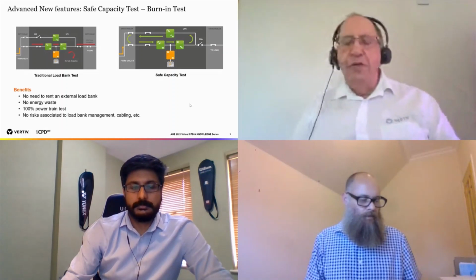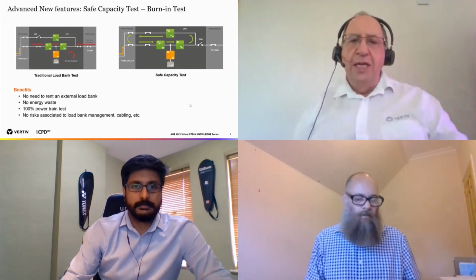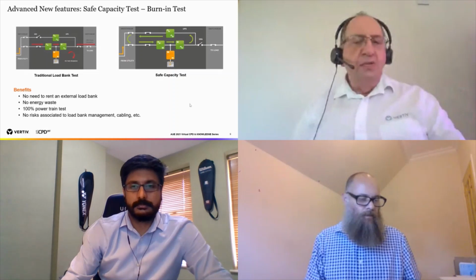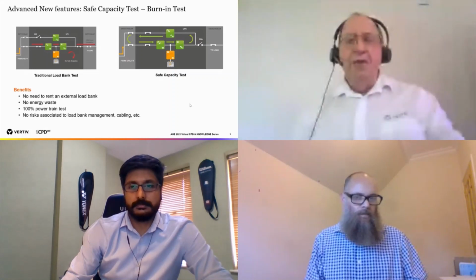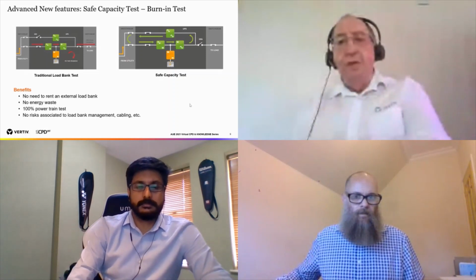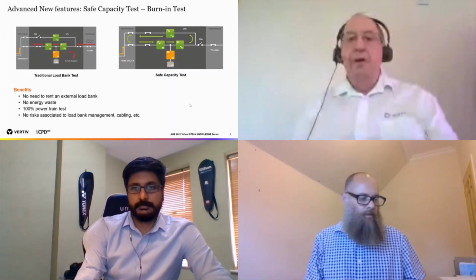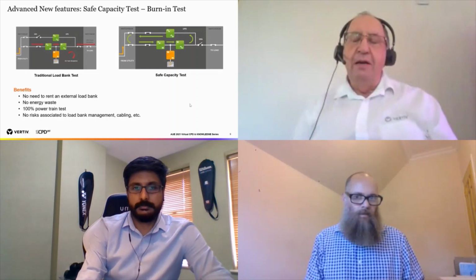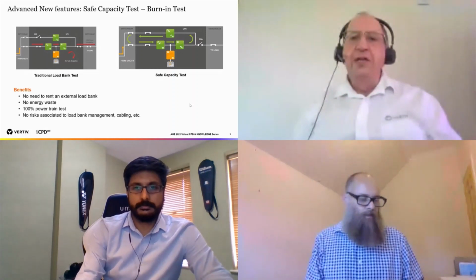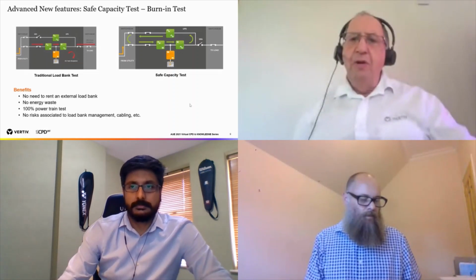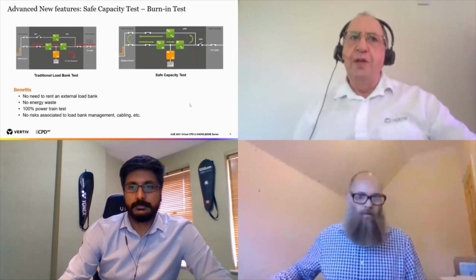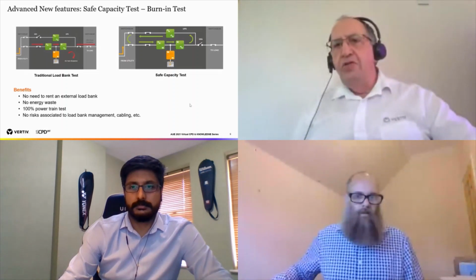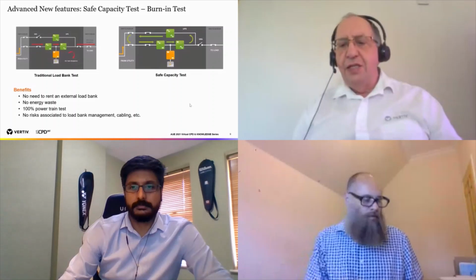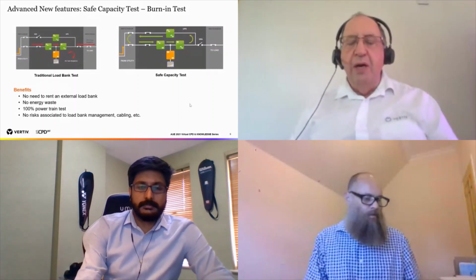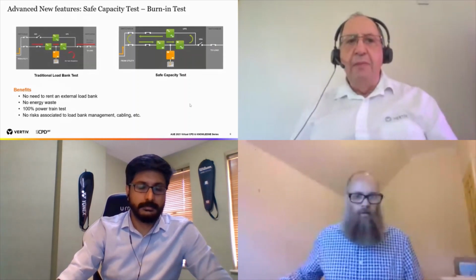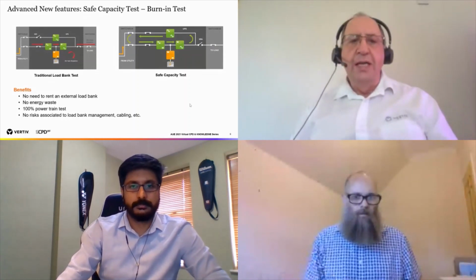And Vertiv, we call this a safe capacity test. So the idea is that we don't need to rent a load bank. Really we're using the building, the load on the UPS, and topping that up by throttling the rectifier. And in so doing, we are testing not only the UPS and battery, but the infrastructure within the room, the cooling system, etc., etc. So that's a new thing that is coming along, and obviously it uses the same cable and switch gear that you've already got connected.